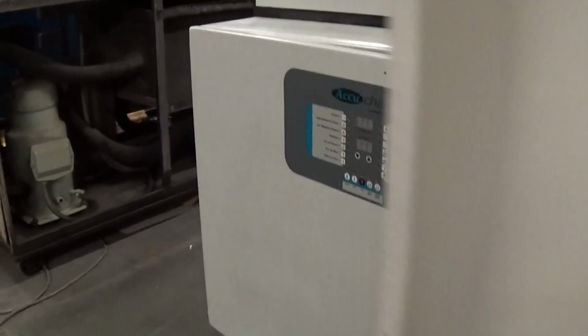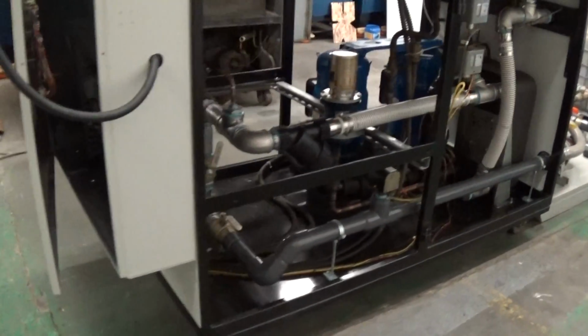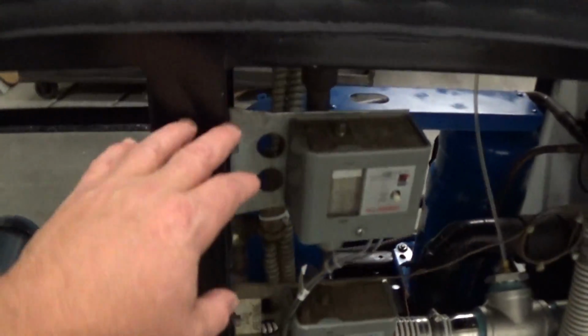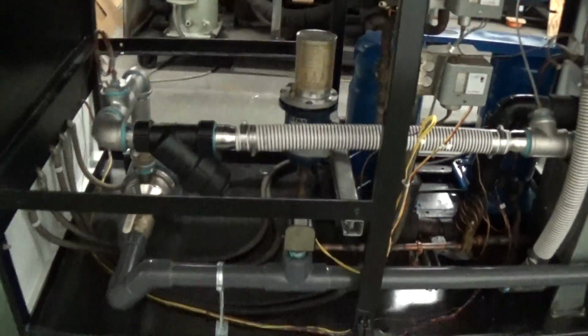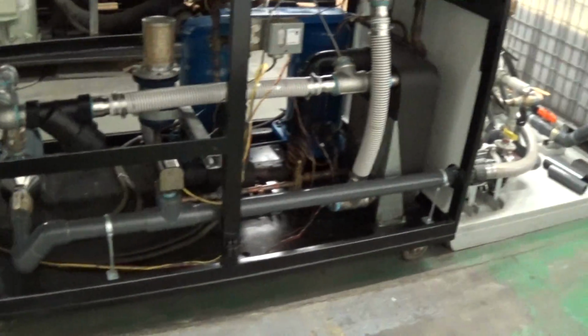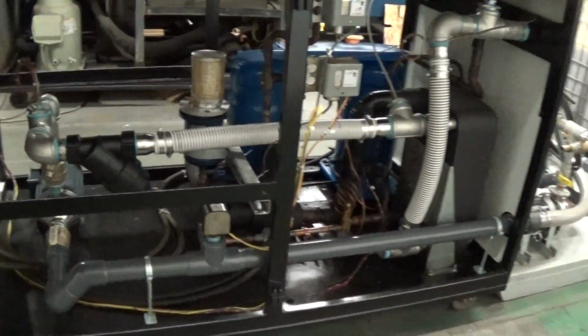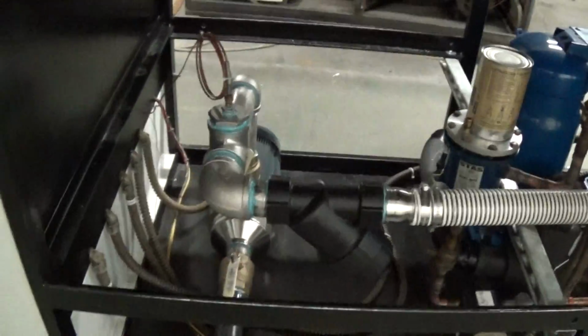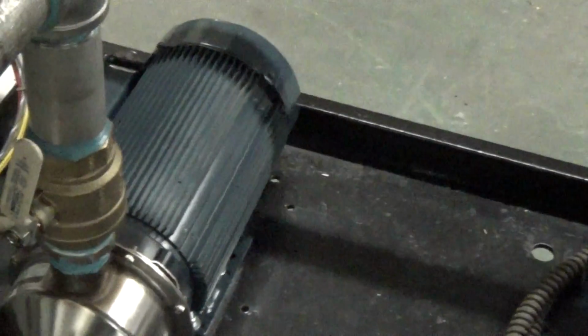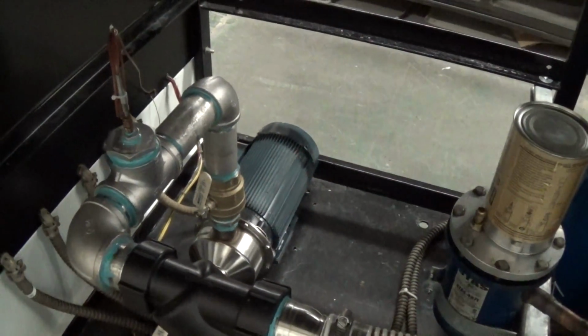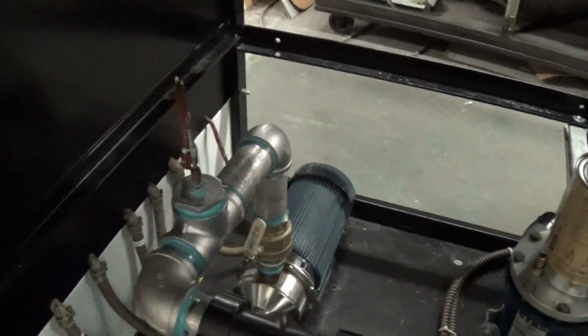We're going to start by, actually before we put the power to the unit, we'll talk about a couple things. For this test, for the lower side cut, we don't have to have the lower side covers on. We do have all these brand new doors with new hardware that pop right on these hinges here. So this we would consider a substantial refurbishment. We took the tank out of the unit because this is a tankless application for the customer. Put in a brand new 5 horsepower water pump, and brand new piping here.